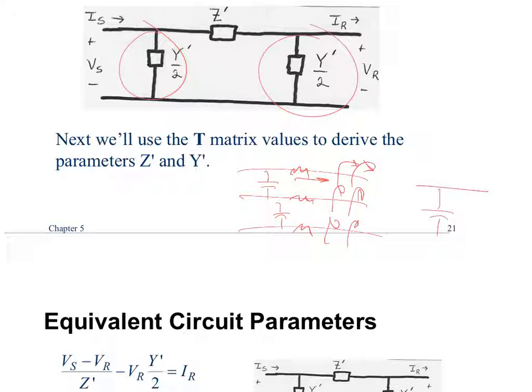These magnetic fields interact with each other, and that's where the inductance comes from. So the capacitance, resistance, and inductance are just from the construction of the line, and this is distributed over the entire length of the line. This capacitance lives everywhere along the line. So instead of putting all the capacitance at the beginning of the line, I put some at the beginning and some at the end. As long as that capacitance is modeled with those two capacitors, I'm accounting for the effect of having one half on one end and one half on the other, in case power flow changes direction.